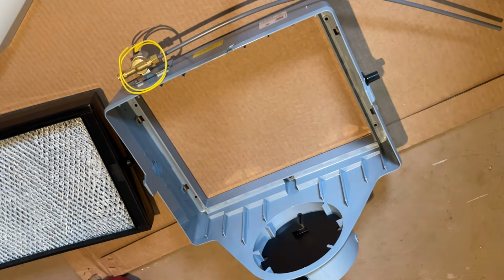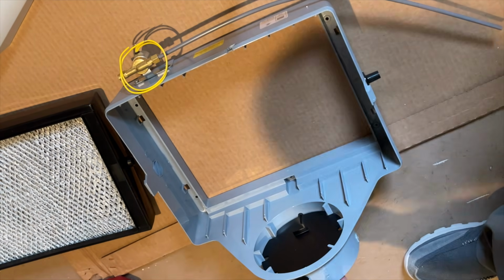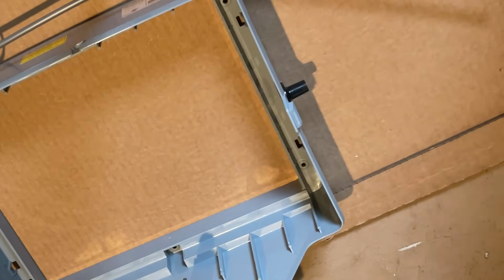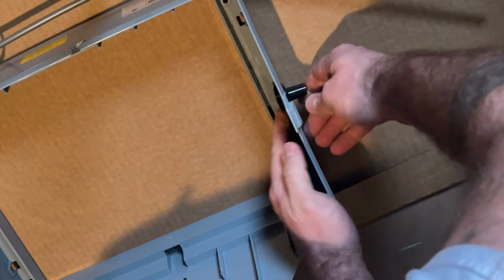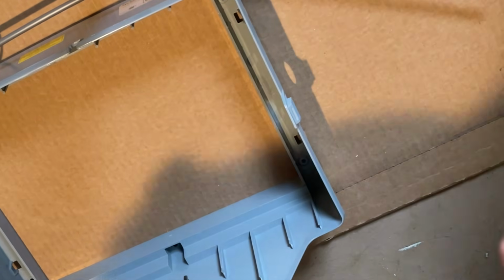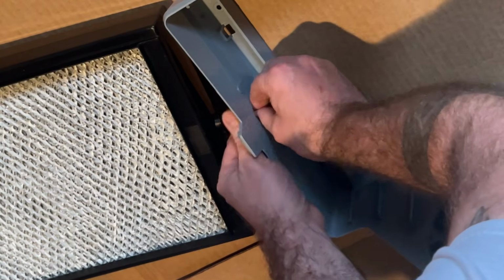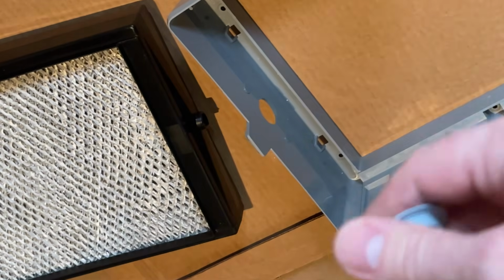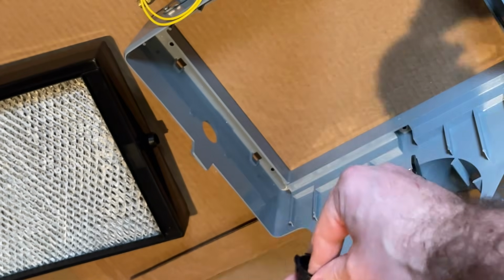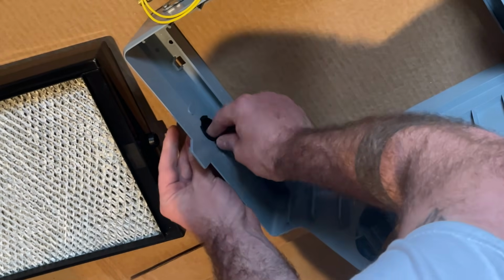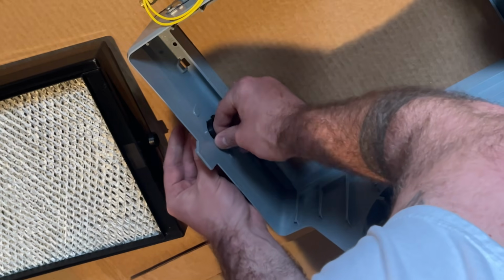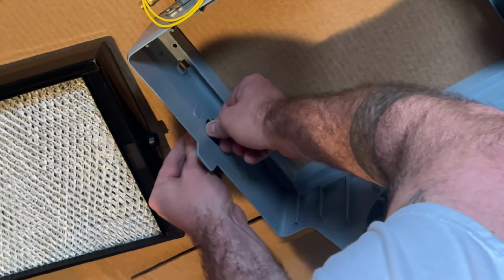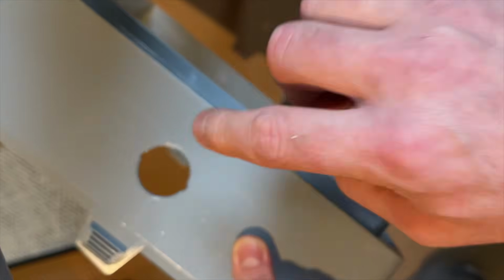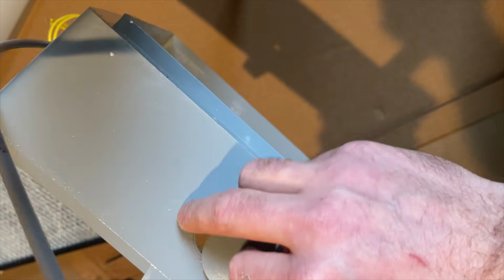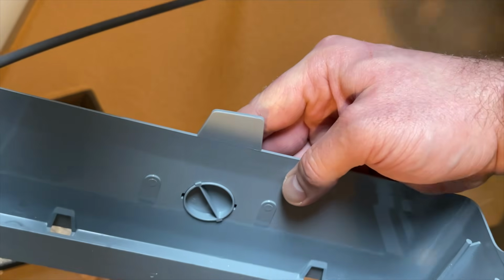We want the system to flip so the intake is coming out of the right side, which is pretty simple. You want to flip the drain and the top plug. They both come out with a slight twist, but the drain comes out on the inside of the system and the top plug is removed from the outside. You flip them and install the drain from the inside with a slight twist, and then install the top plug from the top the same way with a small twist.